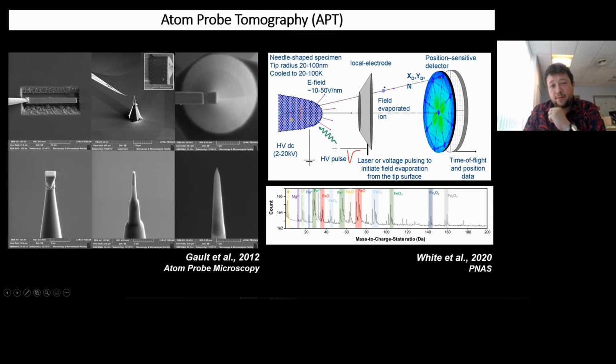So these are ready-made sample holders for the Atom Probe. We park it on, we cut off the very end of our lift out. So you can imagine there'd be just this bit here, we snip it off. That leaves us with this kind of morphology, which we then apply the FIB in a circular motion until we mill it down into a fingertip shape. So as you can see here, this is less than 100 nanometers at the very tip.